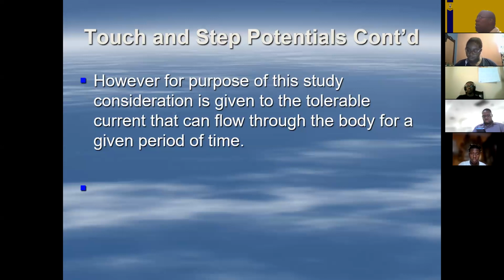Now, you would have heard recently there was a complete system collapse in Trinidad. That is something that really should be unheard of, because they operate a system where the utility company basically provides generating resources or fuel to the generators, and all the generators do is produce the electricity and sell it back to the company. So when that happens, you know there had to be significant system failure. It's just that a fault wasn't cleared in time, and it escalated until the entire system was out.